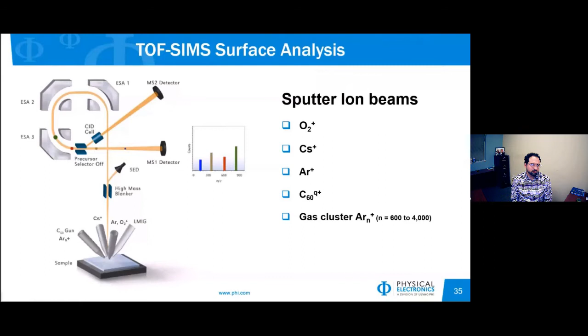It shows less preferential sputtering between inorganic and organic, so depending on your material. And then gas cluster ion beams work really well and have high sputter rates for organic materials and are less effective at sputtering inorganic. So if you have a mixed material, you probably don't want to use argon gas clusters. So we'll go into showing how TOF-SIMS does depth profiling.